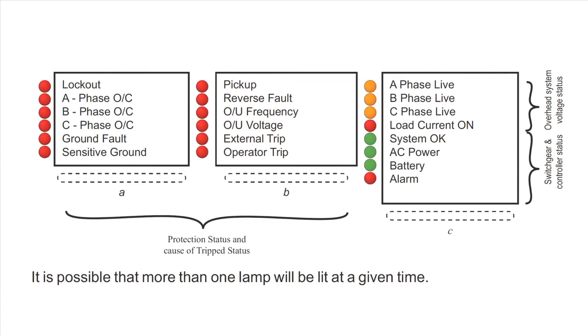In the second column, there are 6 LED status lamps, all of which are red when activated. Pickup. One of the protection elements detected a value outside the preferred range. For example, when the phase current exceeds the trip setting value. Reverse fault. Protection has operated in the reverse direction due to power flow from the load side to the source side of the recloser. OU frequency indicates that an over or under frequency event has caused the recloser to trip. OU voltage indicates that an over or under voltage event has caused the recloser to trip. External trip. An external device has instructed the controller to trip the switchgear. Operator indicates that a local or remote operator has tripped the recloser.